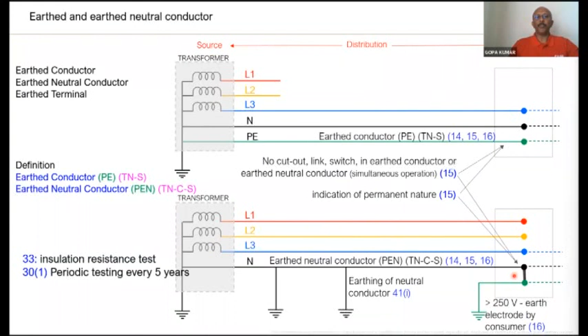But if we analyze, for this particular purpose, here I am showing you a kind of meter board where between the neutral and earth a link is made. Sometimes this creates confusion. How to handle that confusion? The IS code of practice, IS 732, for example, figure number 61, explains how to make the meter board for a low voltage consumer. If you are getting an earthed neutral conductor from the electricity supplier's premise, how to make the earthing at the consumer premise, how to make the earth terminal. These are very well explained.